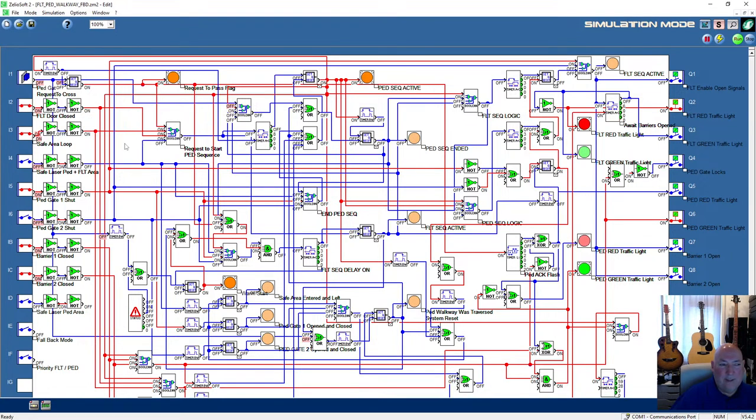So let's just pretend I'm still in the safe area, which I am now. I'll shut the pedestrian gate. Safe area, I'm still in. As long as it doesn't switch and lock them in. I think it will lock them in, but it won't switch the traffic light. But this is what we're trying to avoid: stop them locking in till they've left the area. But not from the loop off the forklift, it needs to be off this new area. See what happens.